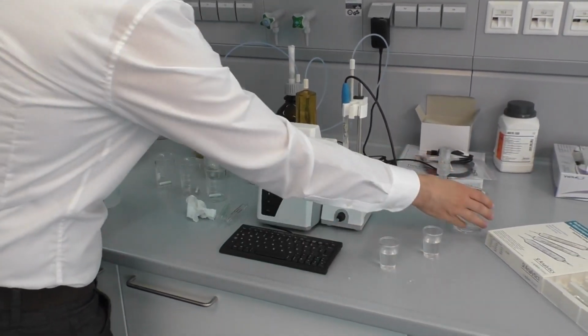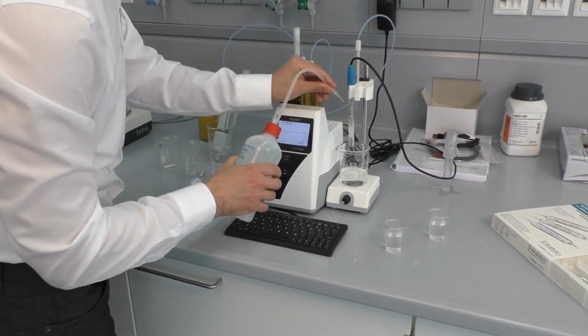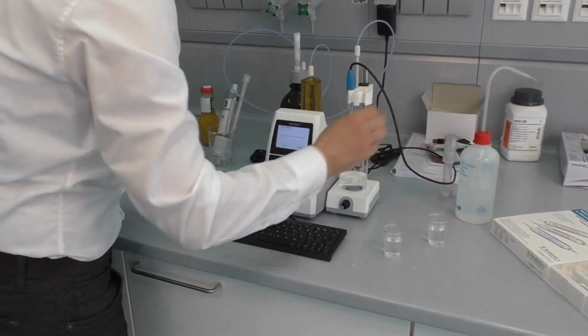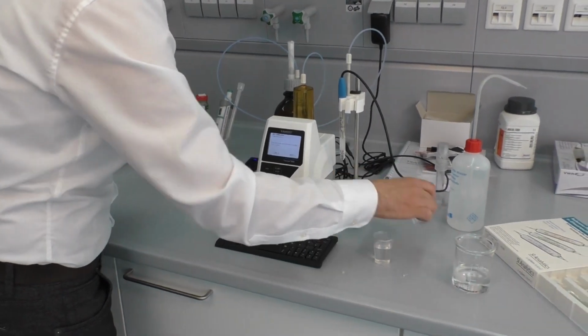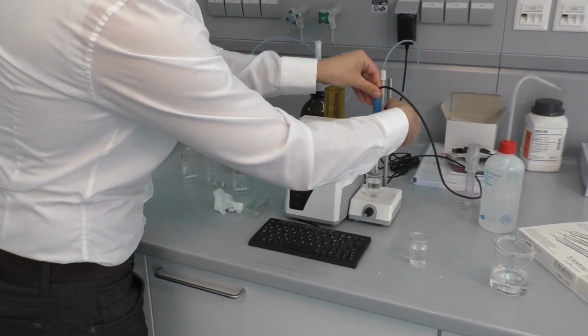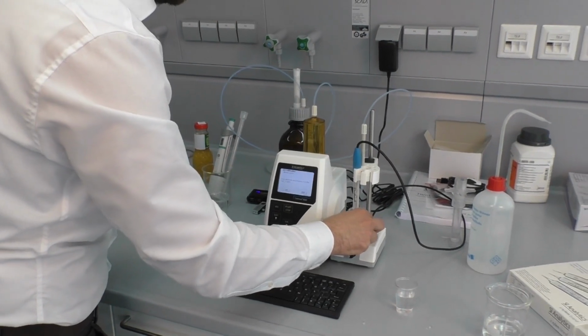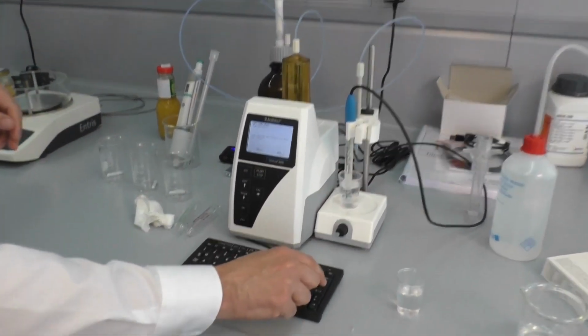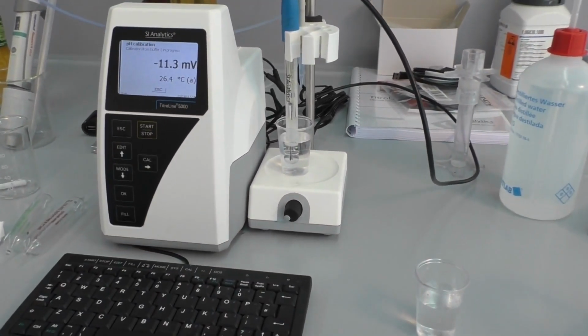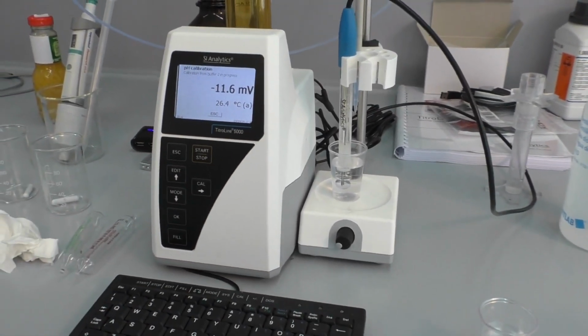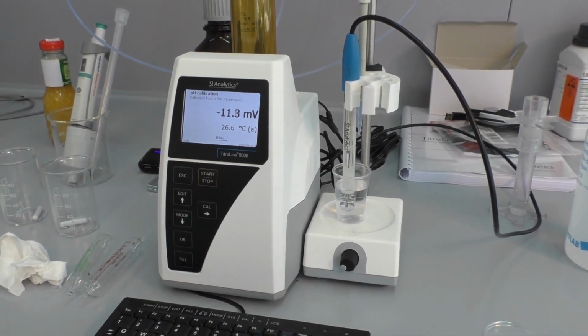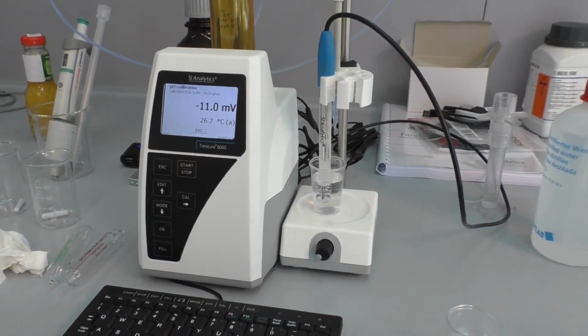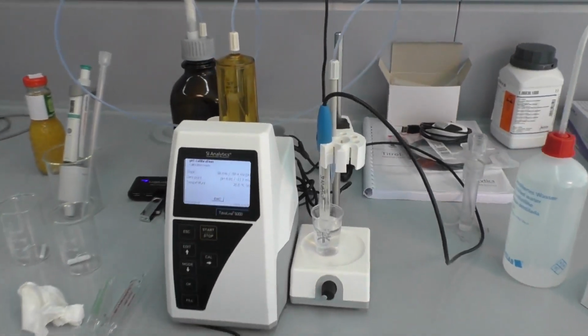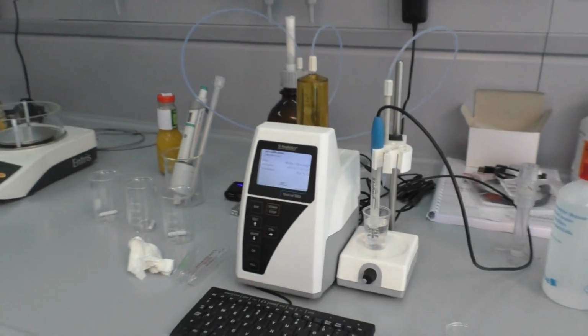Again, the titrator asks for the next step. Again, we are rinsing the electrode, using the second pH 7 buffer, and then starting this second point calibration with enter. When the calibration is ready, the result is shown in the display and the PDF of the calibration result is printed on the USB stick. Now we are ready to measure the sample.